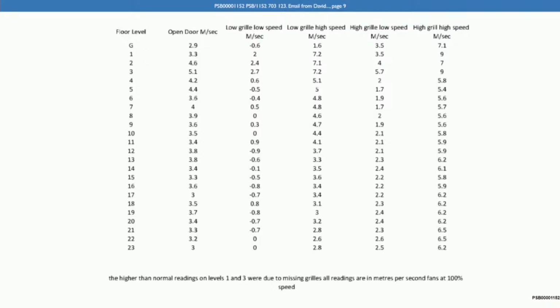And I think what you're saying on this page 9 is that for each floor level, the figure we then see in the second column under open door metres per second is the average figure that you took with the anemometer. It doesn't tell us there that it's an average, does it? No, but that's what it was. That was the average reading per door. And they were the average readings on the grills as well. So on the grill, there were 2 grills, probably took 4 on that, which was 1 shaft. And that was the north shaft and south shaft. So where it says high grill, high speed, that's the north shaft. So the average velocity on that grill was per that reading. And then the low grill, high speed, was the average velocity on the other. Yes, I see.